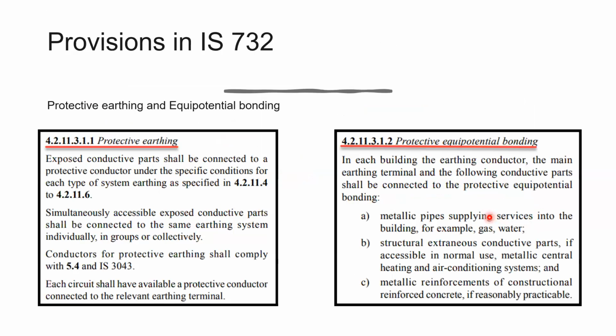Now, in case of the protective earthing, it mentions the exposed conductive parts. It should be connected to the protective conductor based on the network type, which are specified in clauses 4.2.11.4 and 4.2.11.6. So 4.2.11.4 is basically talking about the TN systems, 4.2.11.5 talks about the TT system, and 4.2.11.6 talks about the IT system. And the exposed conductive parts should be connected to the same earthing system individually or collectively in groups.